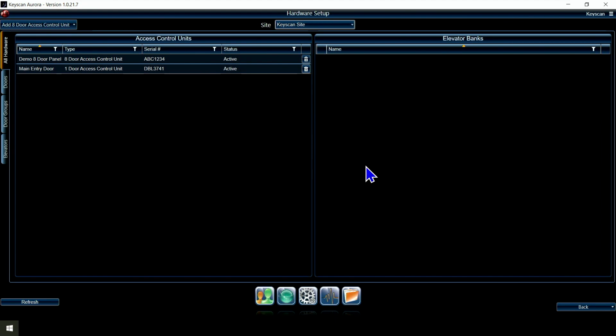I believe the default IP address is 192.168.100.100, I think, but verify that on your paperwork. You can take your laptop, set it to something similar, plug in the panel, and run the configuration software to set it. Or the way I do it is I have the little USB to RS-232 cable that I plug into the panel, run the configuration software, send the IP address to the panel, quick and easy, and I don't have to mess with the network settings on my computer.